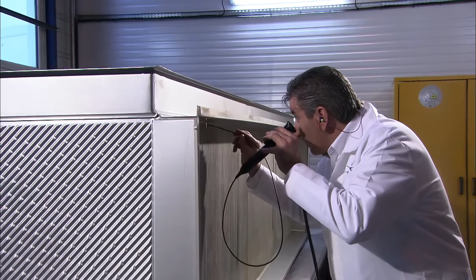An endoscope is used to verify the results of the cleaning. Endoscopic examination is very important because it's the only way to check the chemical cleaning between the plate pack. It also allows checking for internal leakage, and it's possible to take photos to check the welding.